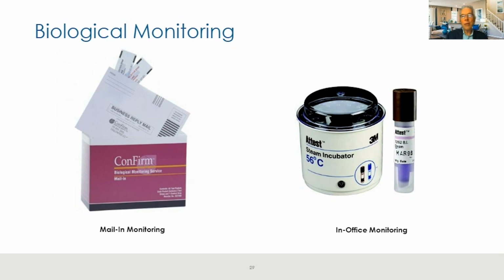If I get a test back showing the autoclave failed, I know the odds are about 70% that the test was just wrong or run improperly, and the autoclave is actually okay. I can reach under the counter, get the in-office monitoring system, and if it's the new one from 3M, I can get results in less than half an hour and get my autoclave back online. So I like to have both.